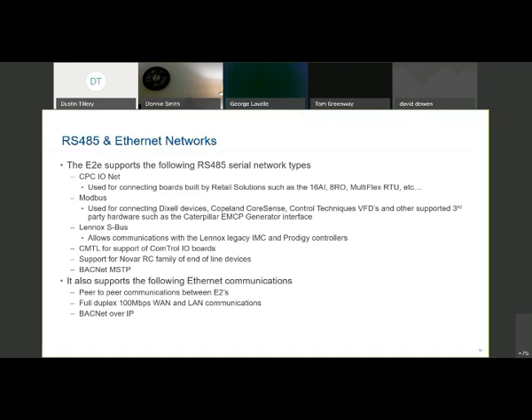So the I/O network is used for connecting boards that are built by Retail Solutions, Emerson, now instead of CPC. Things like our input boards, our output boards, MultiFlex RTUs, ESR boards, those types of devices would be communicating back to the E2 under the I/O network. Then we have the Modbus form of communications for things like our Dixell devices, our universal XRs, CoreSense modules, leak detection panels, things like that that are going to speak on the Modbus.